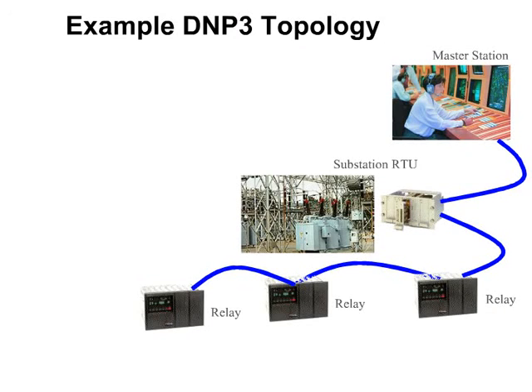Let's look at an example topology. For this example, we'll be looking at a typical substation, although many other topologies are in use. The master station communicates with the substation RTU via DNP. The substation RTU, in turn, communicates with multiple relays, also using DNP. The connection between the substation RTU and the relays can be serial point-to-point connections such as RS-232, serial multi-drop connections such as RS-485, or via a local area network or LAN.